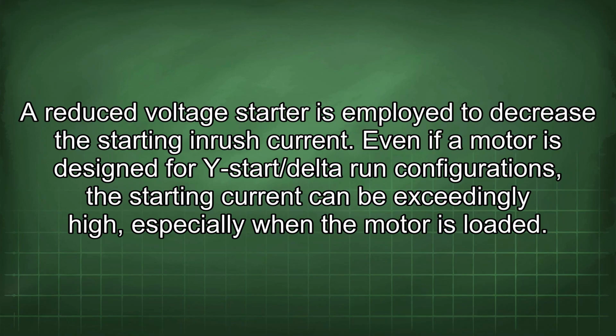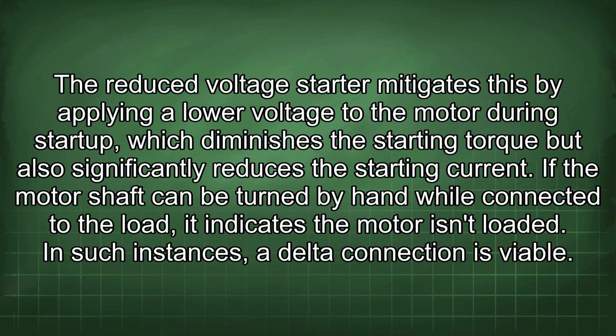A reduced voltage starter is employed to decrease the starting inrush current. Even if a motor is designed for Y-start/delta run configurations, the starting current can be exceedingly high, especially when the motor is loaded. The reduced voltage starter mitigates this by applying a low voltage to the motor during startup, which diminishes the starting torque but also significantly reduces the starting current.